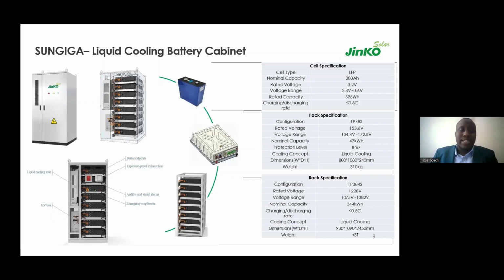The battery cabinets have one liquid cooling plate, that is the battery pack, the liquid cooling plates, and also the liquid cooling unit, and the high voltage box for termination of all the battery connections. We've also integrated a fire suppression system and explosion-proof design.